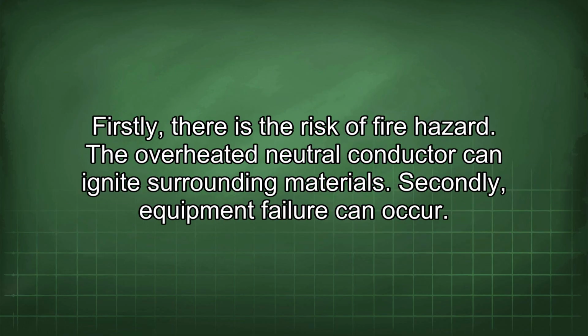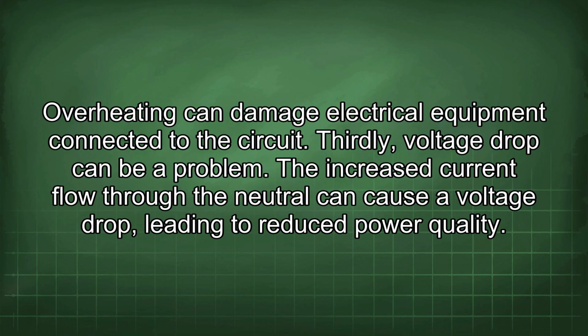Firstly, there is the risk of fire hazard. The overheated neutral conductor can ignite surrounding materials. Secondly, equipment failure can occur. Overheating can damage electrical equipment connected to the circuit. Thirdly, voltage drop can be a problem. The increased current flow through the neutral can cause a voltage drop, leading to reduced power quality.